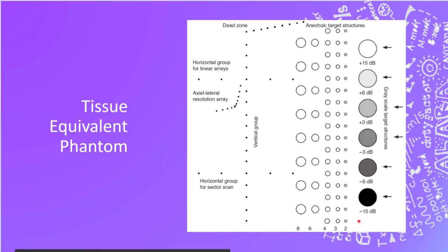We want to make sure that we don't have misregistration of grays in a bright spot. We also want to make sure that we don't have this anechoic structure appearing with echoes within it. And then we have spaces in between here that tell us that we should progressively be getting darker. If these are all the same level gray, then something's wrong with the calibration of our machine. So this again tells us that we're going to get the right grays for what we expect on the machine.